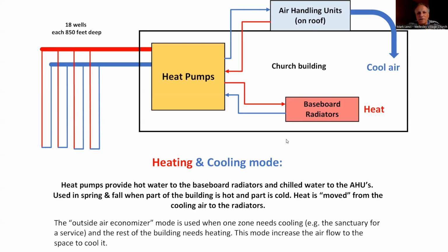The other thing is the heat pumps, compared to air source heat pumps, can be designed to operate in a 10-degree temperature range. So you can build a much more efficient heat pump than you can for an air source heat pump that has to go between -10 and 100 degrees outside air temperature. All this adds up to efficiencies in geothermal that we didn't have a way of putting any numerical values to, which we were just guessing when we went into this, but it's turning out really efficient. Okay, next slide.